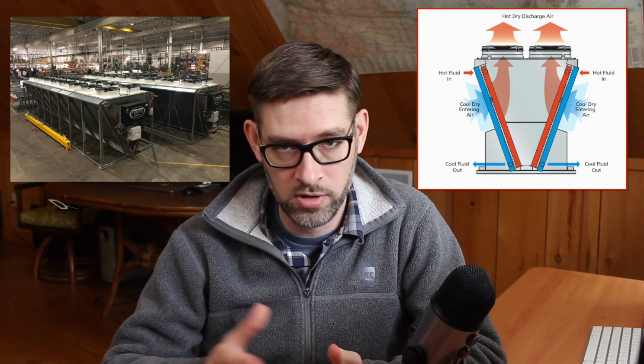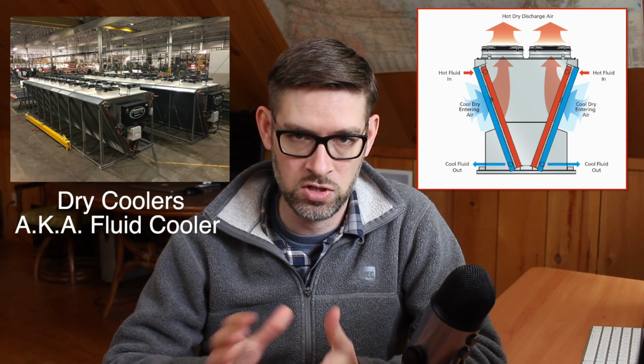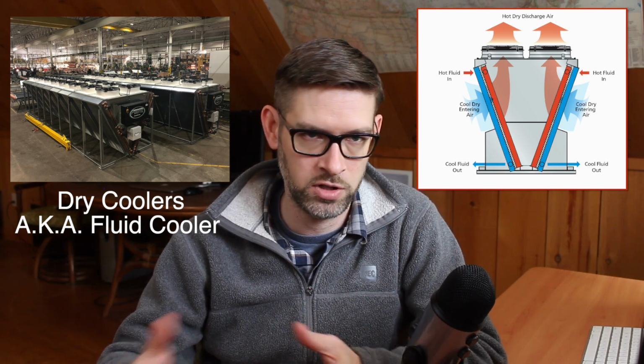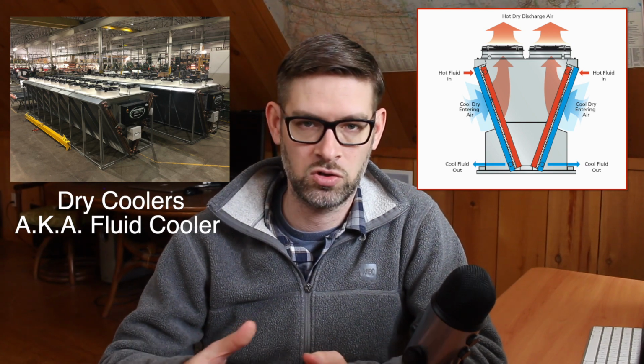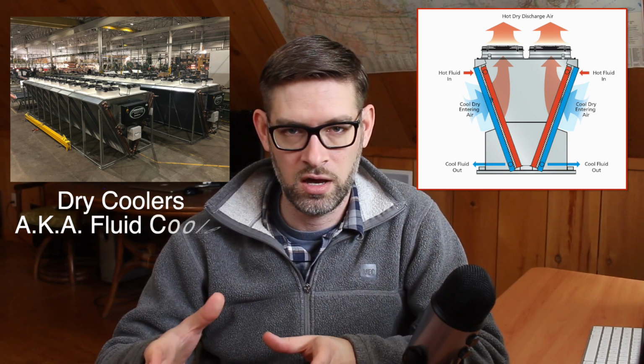The purpose of any cooling tower or evaporative cooling device is to exchange energy, thermal energy, between a working fluid and outdoor air. Now, on a cooling tower, the fill is the business end of that heat transfer process. Now, you also find fill in evaporative fluid coolers as well. As a side note, dry coolers, as per their name, don't use evaporation to exchange energy. So a dry cooler wouldn't have fill. A dry cooler is simply a closed circuit coil placed in an airstream, and it's rejecting heat from that coil into the airstream.